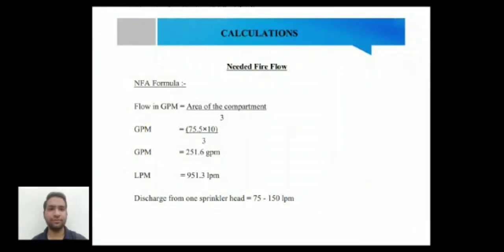Hello sir, my name is Pradyumna Sharma and I will take over from Akash Namdev. These are the calculations of our major project, railway safety systems against fire. We have calculated the total fire flow from the reference of the NFA formula. According to the NFA formula, flow in GPM is the area of the compartment divided by 3. So 75.5 is the length of the railway coach in feet, and 10 feet is the width of the railway coach, divided by 3. Then we calculated that 951.3 lpm water flow is needed.